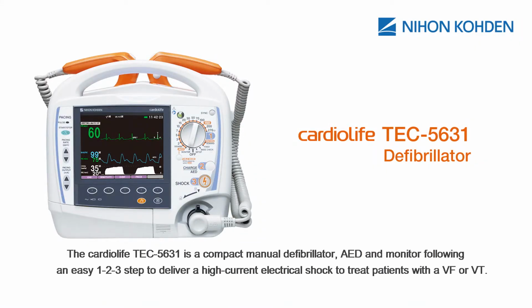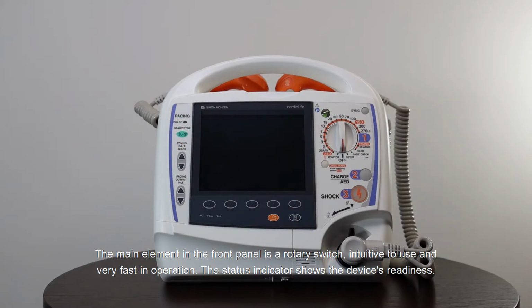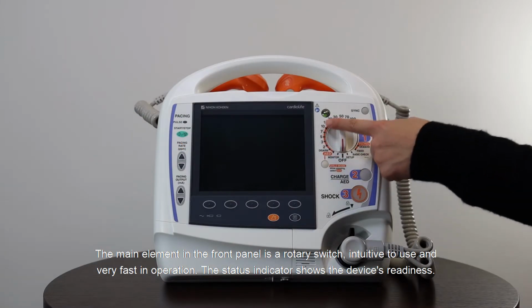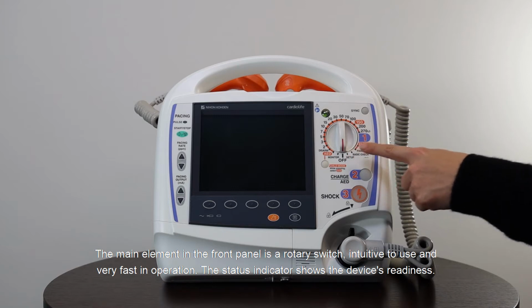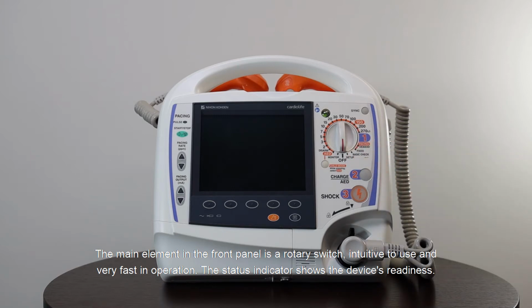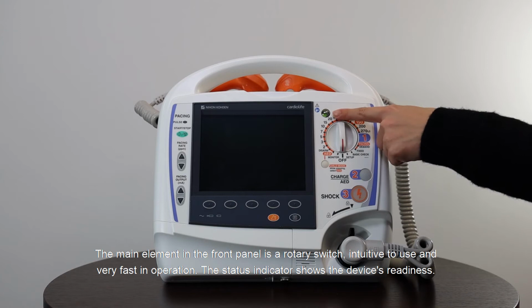The Cardiolife TEC-5600 is a compact manual defibrillator, AED and monitor following an easy 1, 2, 3 step to deliver a high current electrical shock to treat patients with a VF or a VT. The main element in the front panel is a rotary switch, intuitive to use and very fast in operation. The status indicator shows the device readiness.